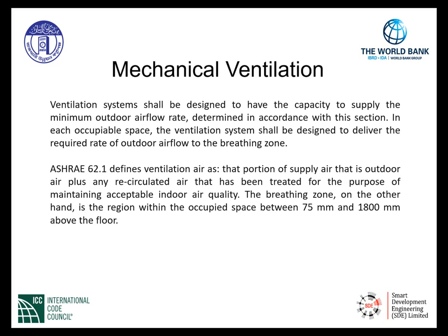Mechanical ventilation. Ventilation systems shall be designed to have the capacity to supply the minimum outdoor airflow rate, determined in accordance with this section. In each occupiable space, the ventilation system shall be designed to deliver the required rate of outdoor airflow to the breathing zone.